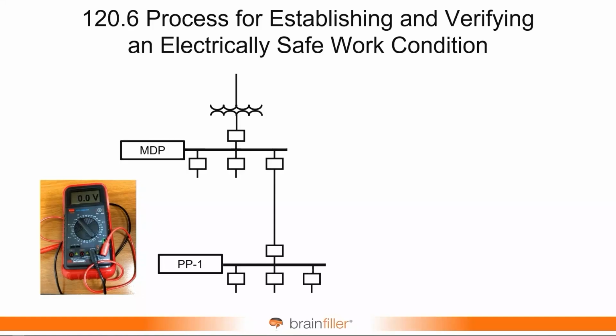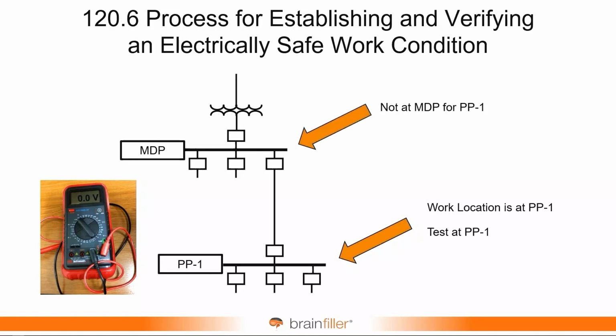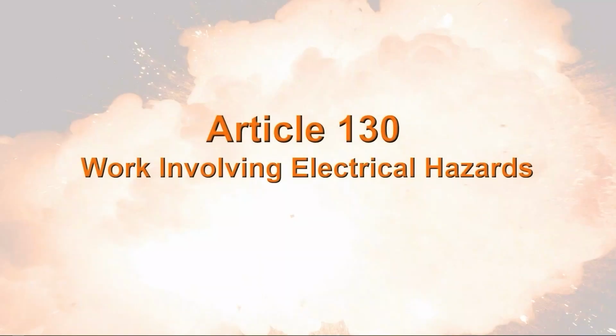And so looking at it in a little more detail, if you were going to be conducting work at panel PP1, and this was to be electrically safe, then you test at panel PP1, not upstream. I mean, you could test upstream if you want, but that's not going to be used to verify absence of voltage at PP1. Work involving electrical hazards. The tables that contain the limited and restricted approach boundaries have had some modifications to them. And I'm going to go over these with you.